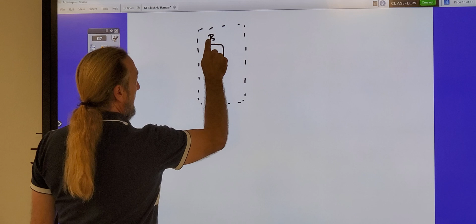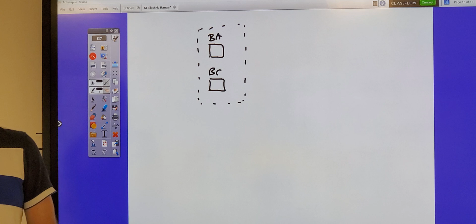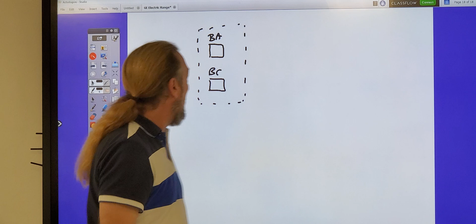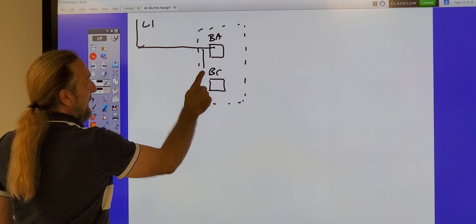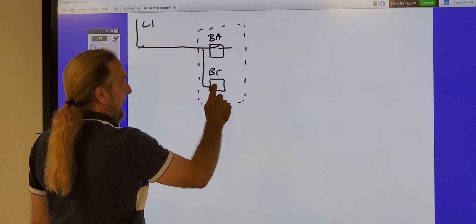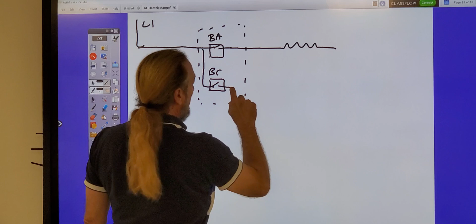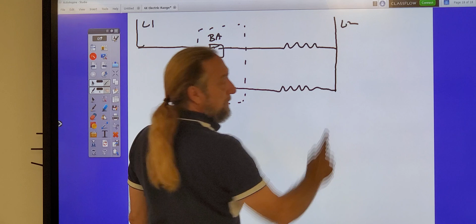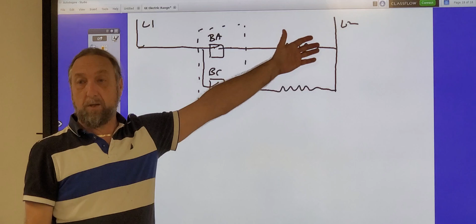Okay, so let's say this is the computer board, and I'm going to draw 2 relays, bake and broil, right here. Now I'm going to do it this way, as this is how it was done old school, back when they first started doing electronically controlled ovens. These are newer designs, a lot of them come out like this now, but how did they do it before? So we had line 1 come in, and line 1 went into one relay, and also went into another relay. They had a switch here and another switch here, and then this one went to a bake element, and this one went to a broil element, and went to line 2. If I wanted bake, I close the bake relay, this one comes on. If I want broil, I turn the broil relay, and the broil works.